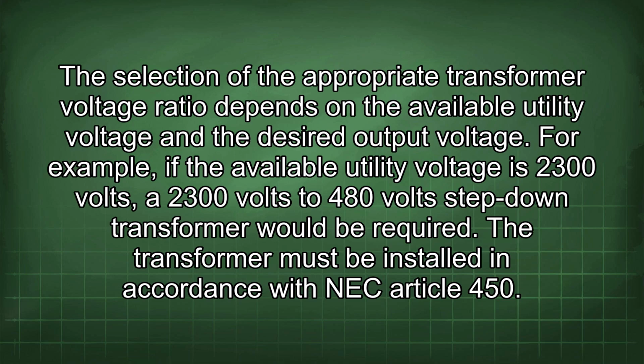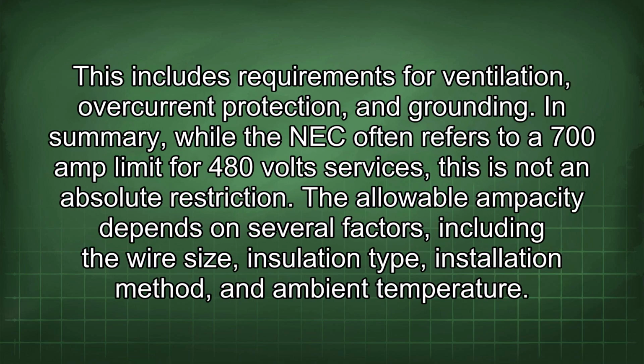For example, if the available utility voltage is 2300 volts, a 2300 volts to 480 volt step-down transformer would be required. The transformer must be installed in accordance with NEC Article 450. This includes requirements for ventilation, overcurrent protection, and grounding.